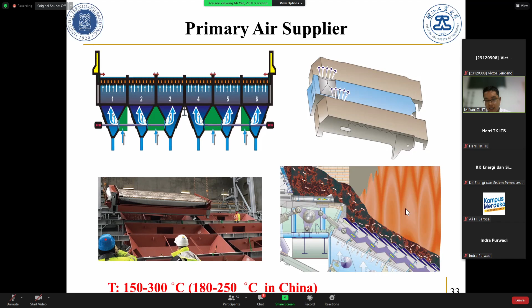And usually the primary air is heated to something like 180 to 220 centigrade. But for the secondary air, usually it is without preheating, at least in China. But now more and more companies have started thinking about using hot secondary air. Because hot secondary air will be helpful to increase the incineration temperature, can reduce the emissions, and will increase the parameters of the steam. So the efficiency will be increased.